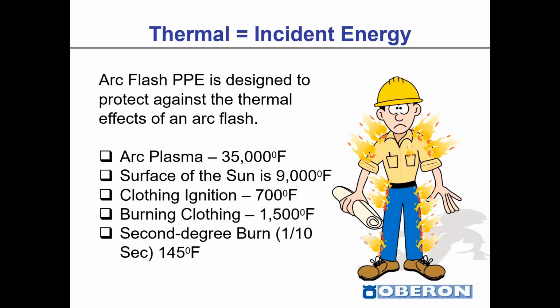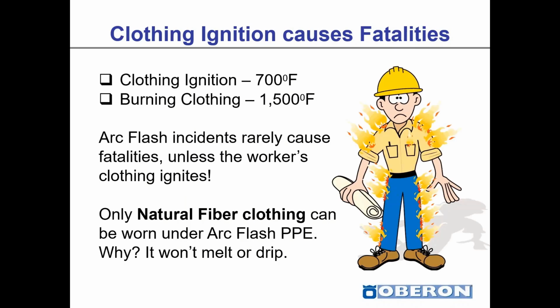Arc Flash PPE is designed to protect against the thermal effects of an arc flash. I have a few different items listed here, such as the arc plasma temperature. The core of the arc flash, or the arc plasma, is approximately 4 times the temperature of the surface of the sun. We have identified clothing ignition, burning clothing, second-degree skin burns. Again, that's about 1.2 calories. The clothing ignition causes fatalities. That's the number 1 leading cause. Arc flashes rarely cause fatalities unless the worker's clothing ignites.